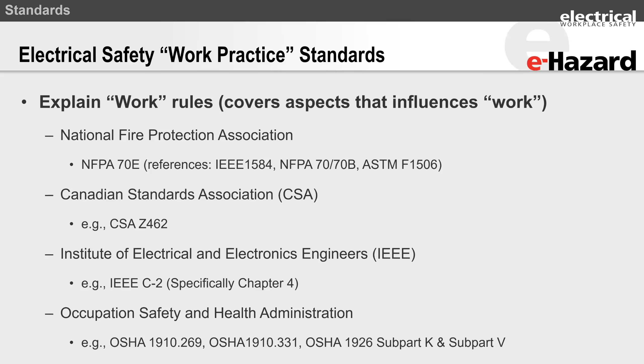What is a mandatory standard? A mandatory standard is one that is enforceable by law, and that law can either be federal or state. So OSHA, when referencing these standards—you've got the OSHA standards themselves, we spoke about subpart S, subpart R, but within those standards, and even in subpart I, 1910 subpart I, which speaks about PPE—it would reference a standard, for example, the ASTM standard D120 for rubber insulating gloves, referenced in that OSHA standard.